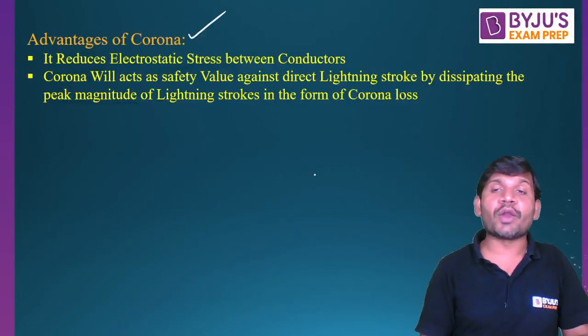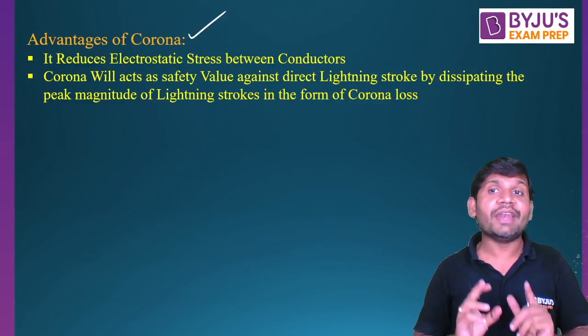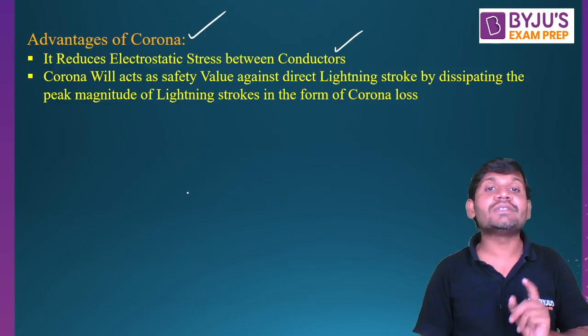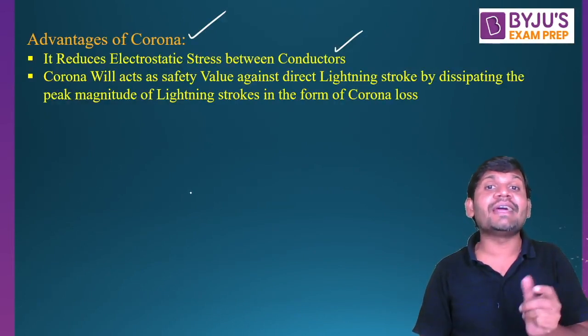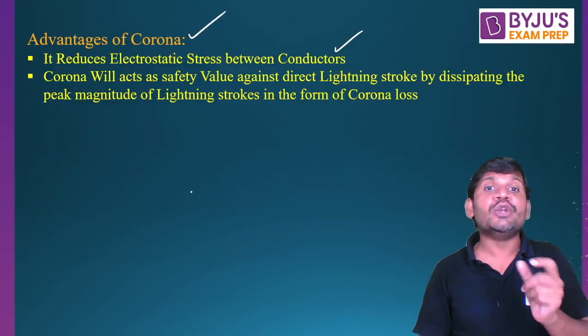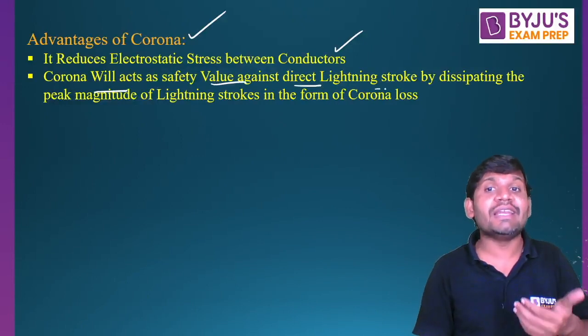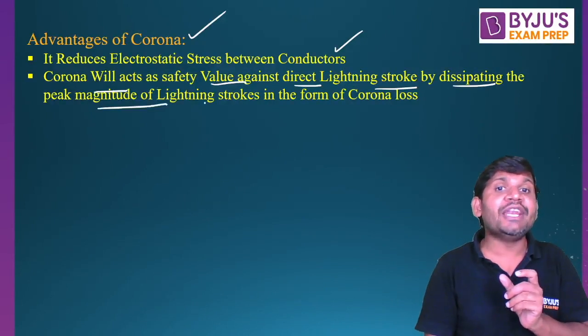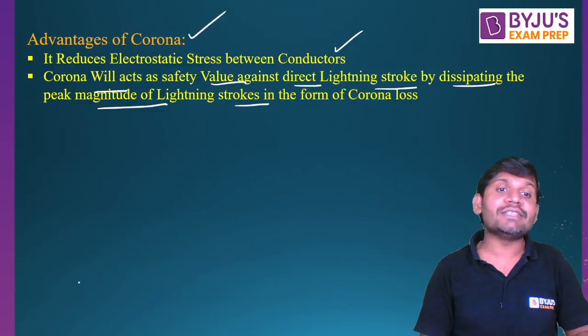What are the advantages of corona? There are many disadvantages due to corona on transmission lines, but there are some advantages as well. It reduces the electrostatic stress between the conductors, because when corona takes place along the line, the effective diameter of the conductor increases. Corona also acts as a safety valve against lightning strokes — if any lightning stroke falls on the line, it dissipates the peak magnitude of the stroke and reduces its severity.